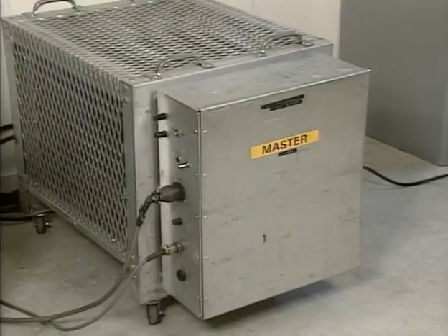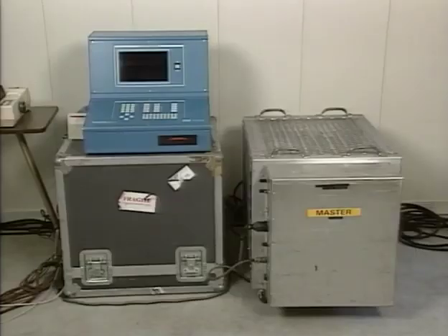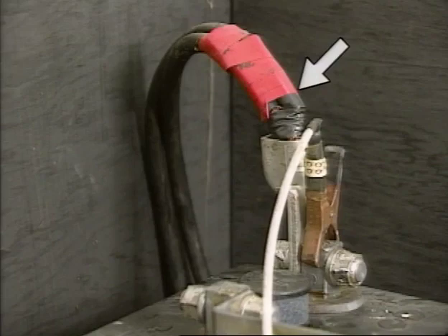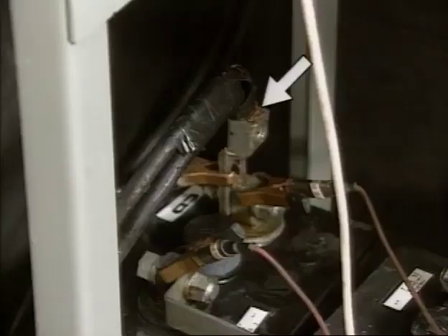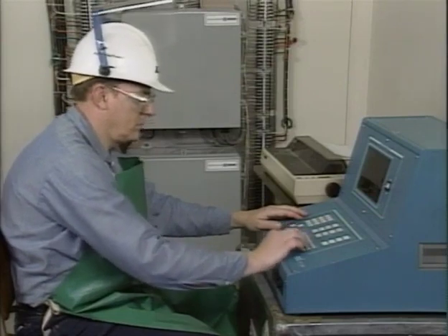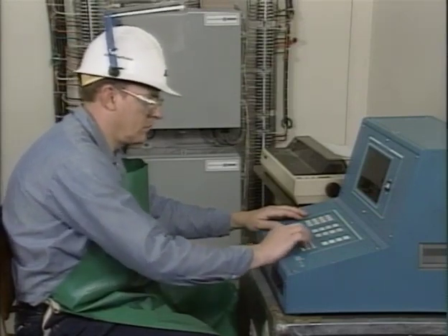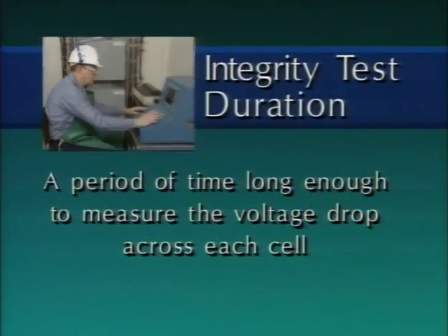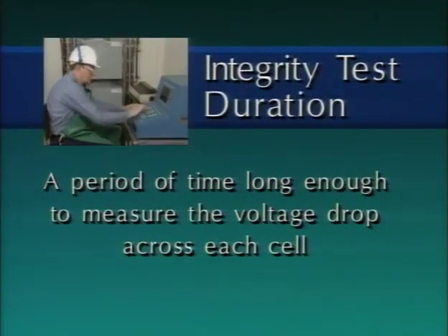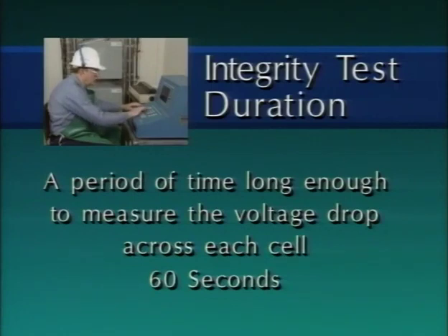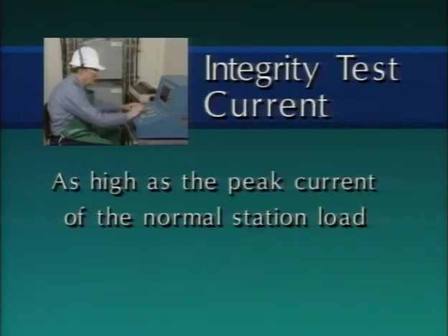The master load unit is regulated by the control unit to draw the required current from the battery. Both units are plugged into an AC outlet. The load unit has two cables, which are connected to the positive terminal of the first cell and the negative terminal of the last cell. Once the equipment is properly connected, the control unit is programmed for the desired test duration and current. For the integrity test, the test duration is a period long enough to measure the voltage drop across each cell. In this case, 60 seconds. The test current is a value that's as high as the peak current of the normal station load. In this example, 70 amps.